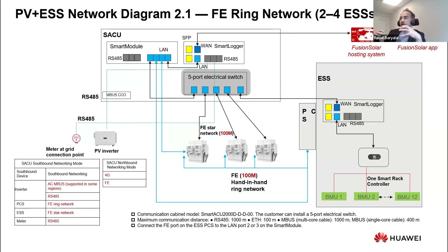Of course, we also have fiber communications, let's say a fiber ring network, if we don't want to use communications through Ethernet. We could use the fiber input on the CMU unit inside the battery for more stable communication, especially if there are huge distances between the ESS and we need a constant good communication. We can use the fiber option, of course, because the CMU and the smart logger sitting in the cabinet have fiber inputs as an alternative for fiber communication. And we could actually connect up to 15 ESS, and fiber networking is completely possible.